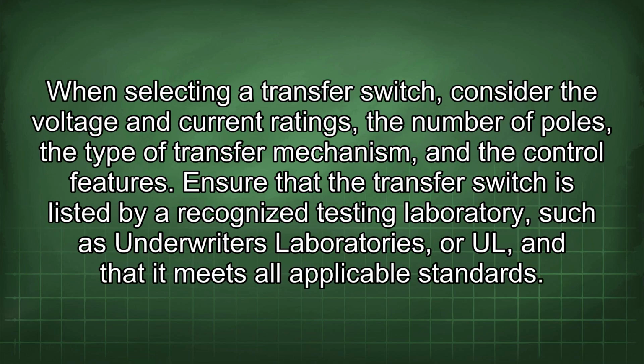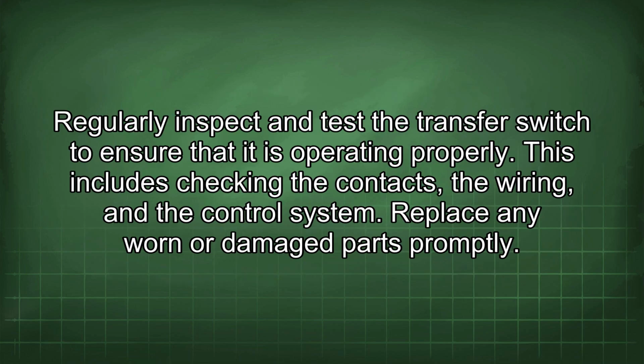When selecting a transfer switch, consider the voltage and current ratings, the number of poles, the type of transfer mechanism, and the control features. Ensure that the transfer switch is listed by a recognized testing laboratory such as Underwriters Laboratories or UL, and that it meets all applicable standards. Regularly inspect and test the transfer switch to ensure that it is operating properly. This includes checking the contacts, the wiring, and the control system. Replace any worn or damaged parts promptly.